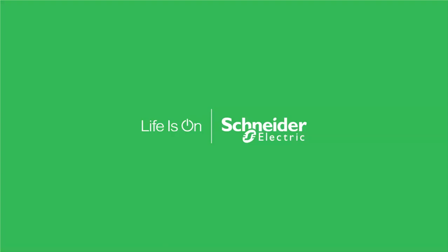Will do. Next question: what logging interval do you recommend for energy or power metering data, and is this interval the same as for PQ logging data? Note that they are not referring to the sampling rate, but the file storage interval for analysis and reporting. For example, they tend to expect a logging interval of 15 minutes, which is equivalent to the timing interval of their electrical utility meter data.